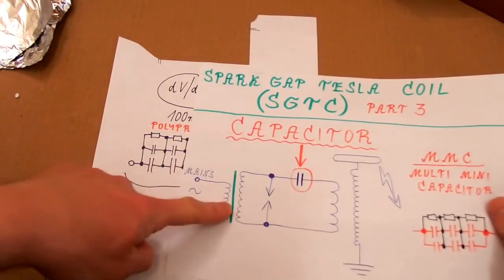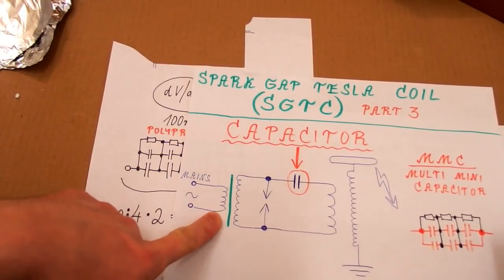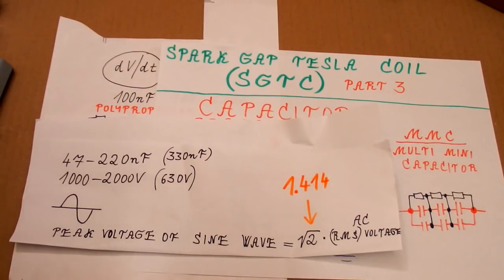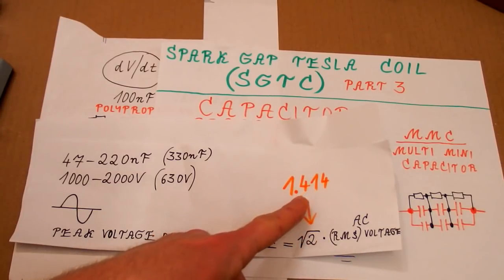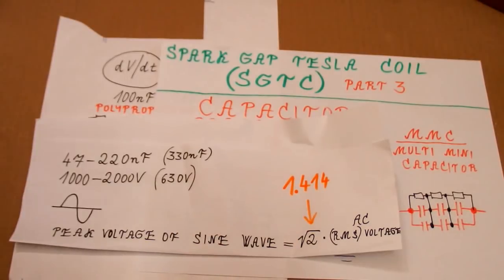Now the question is what has to be the voltage rating of your capacitor bank and how many capacitors you have to put in series. It depends on the voltage of your high voltage transformer, of course. It has to be rated at least for the peak voltage of your high voltage transformer. And the peak voltage of a sine wave AC voltage is the AC voltage times the square root of 2, which is about 1.414. Plus, of course, some headroom. And how much headroom? That's not an easy question. It depends on how reliable you want it to be.